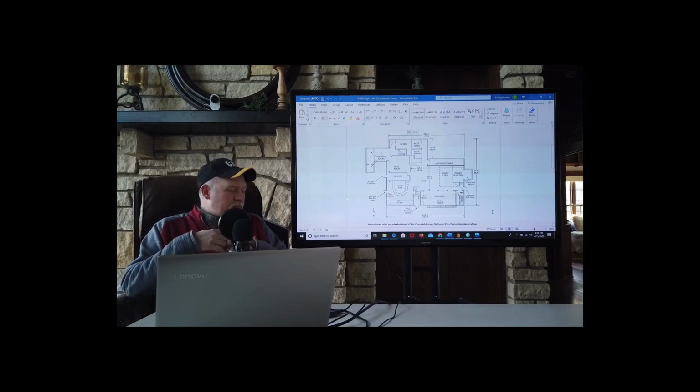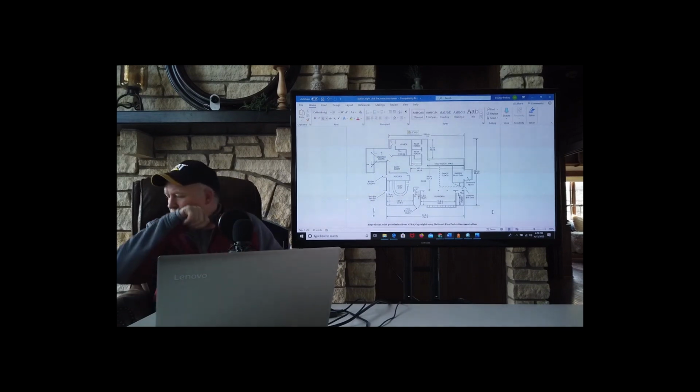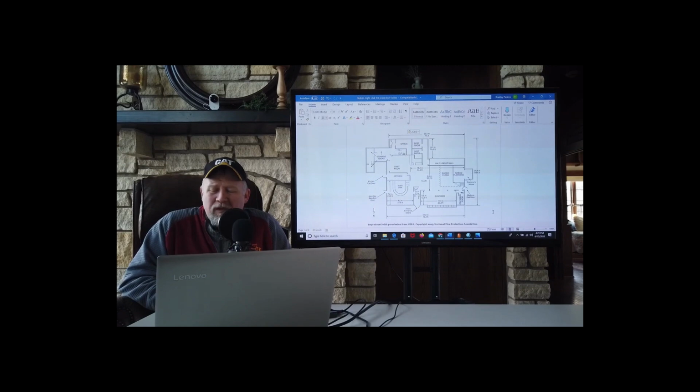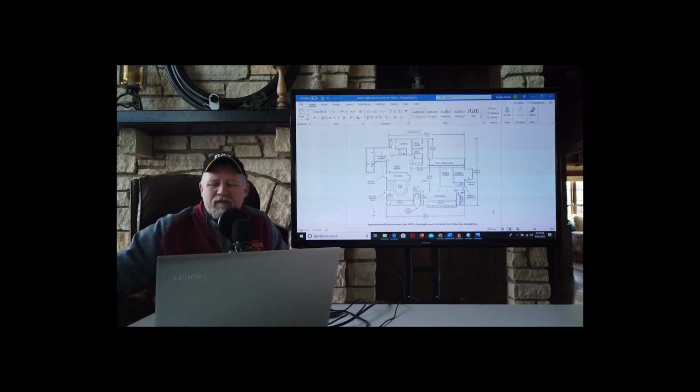Something interesting about this particular fire, though, keep in mind that this club was not required to have automatic sprinkler systems. It was not required at the time that it was built, and it was not required at the time this event happened. However, they could have, and just remember, it would cost right about $3, $4 a square foot.